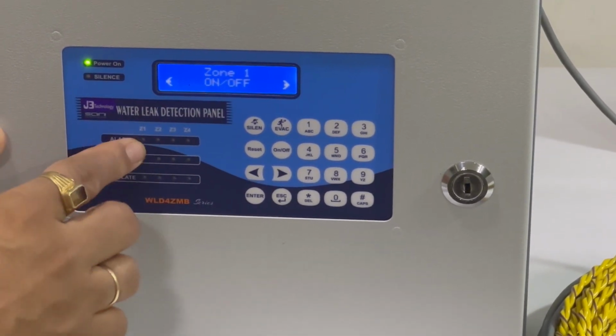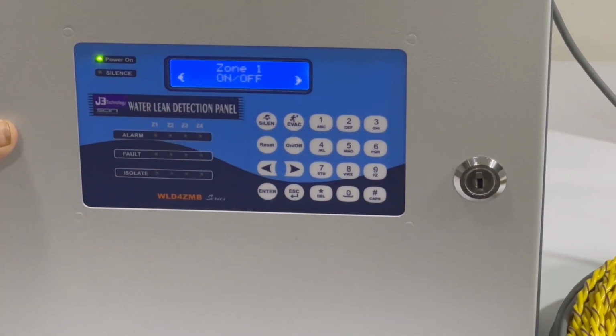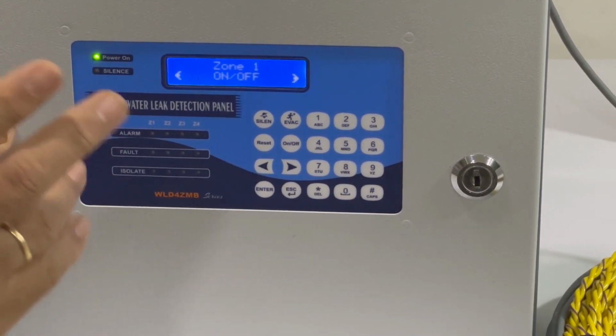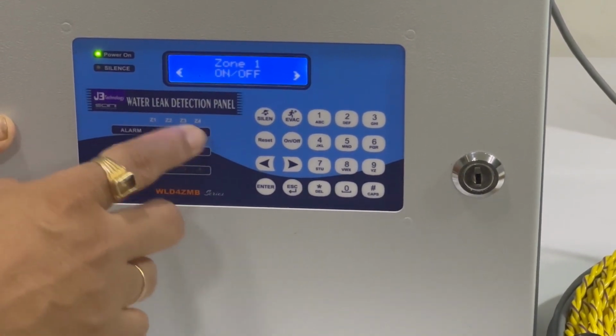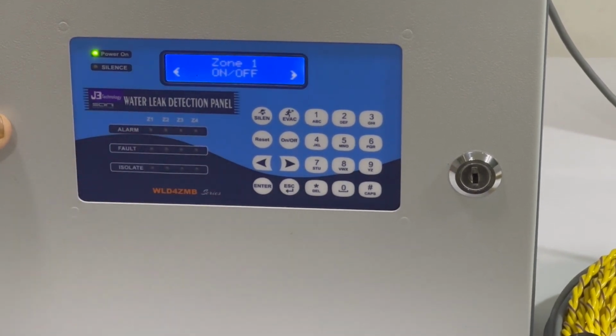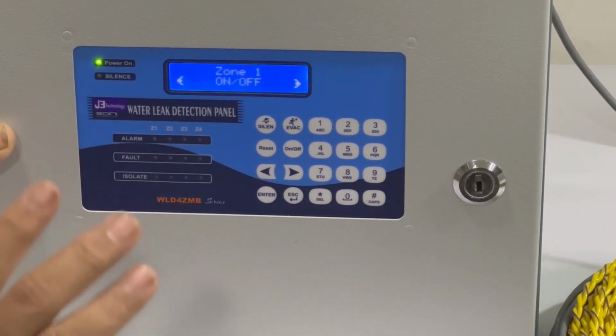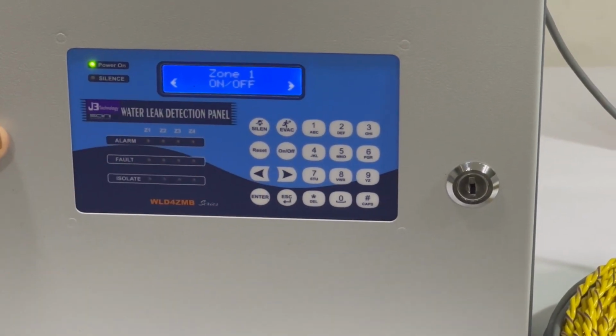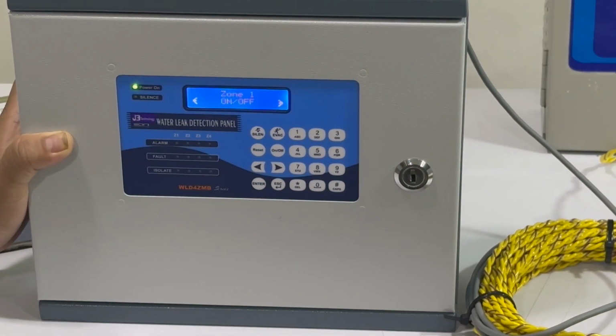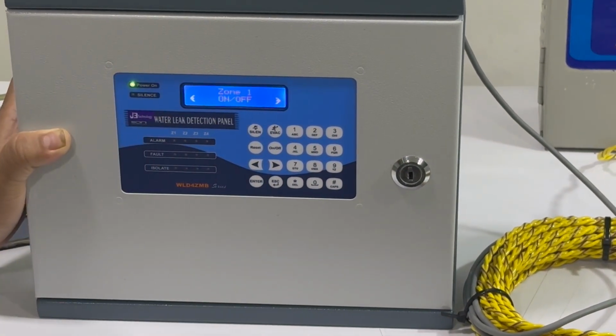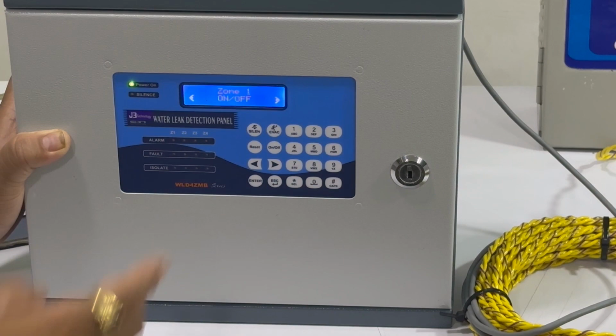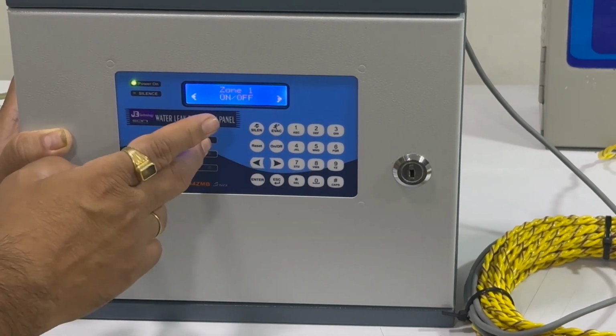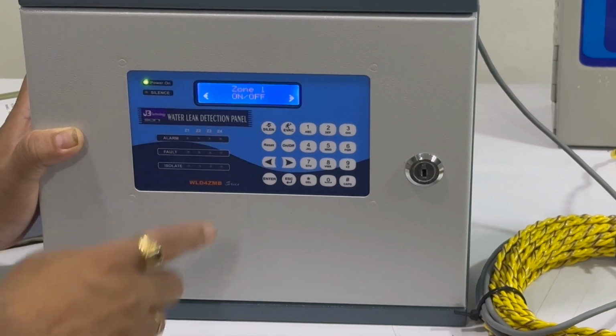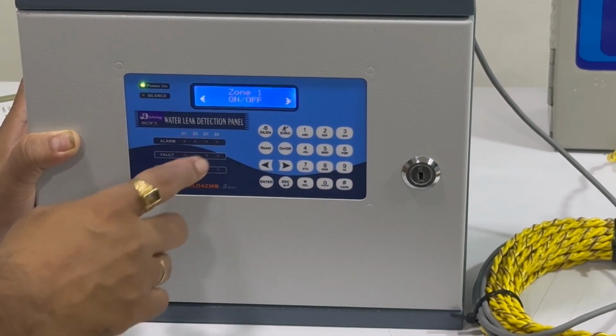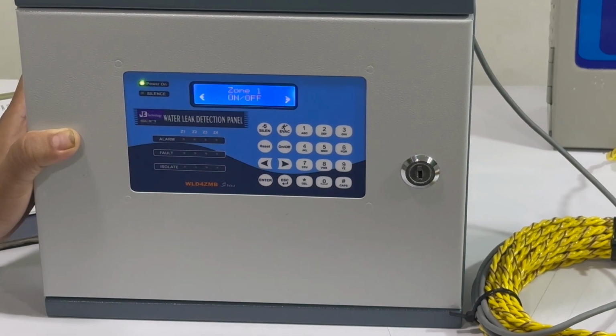So this is purely a 4-zone panel. Suppose you are using 2 zones and not using the other 2 zones. In that case, you have to put the 2 unused zones in off mode and the remaining 2 zones should be in on mode. If you are using 4 zones, then you do not need to put any zone off. It should be on. The reason for this is that, suppose you are using one zone and the rest 3 zones you are not using, and you have not put those zones off, then it will show the fault indication over here, as I will show you by doing the same.